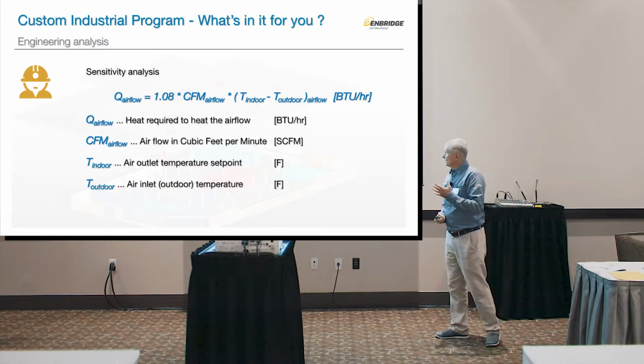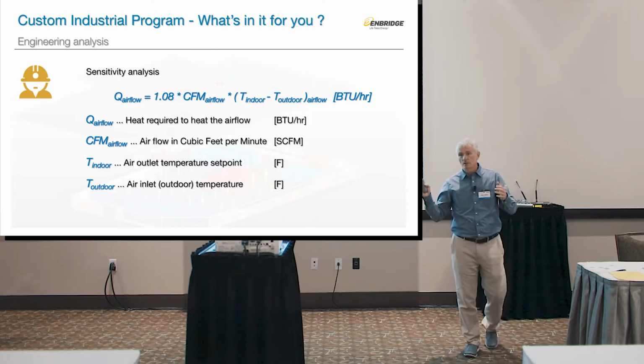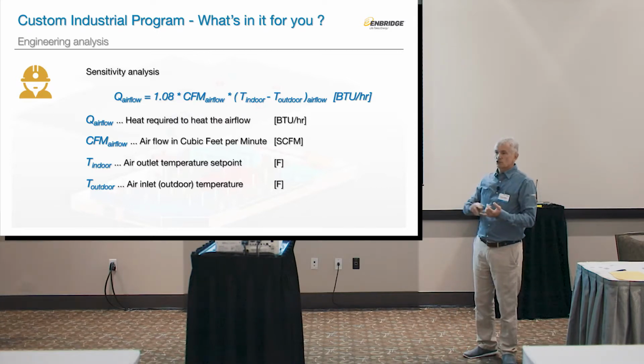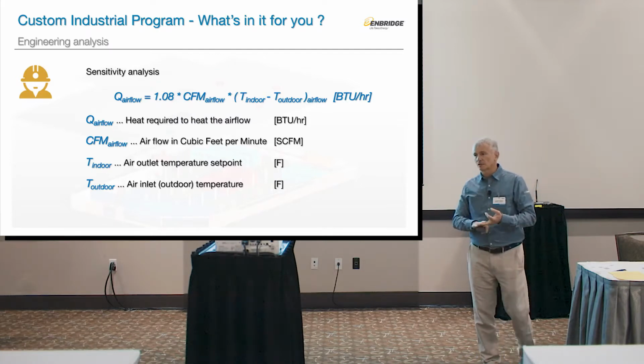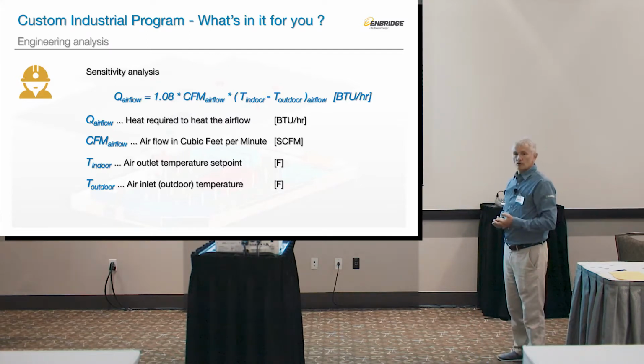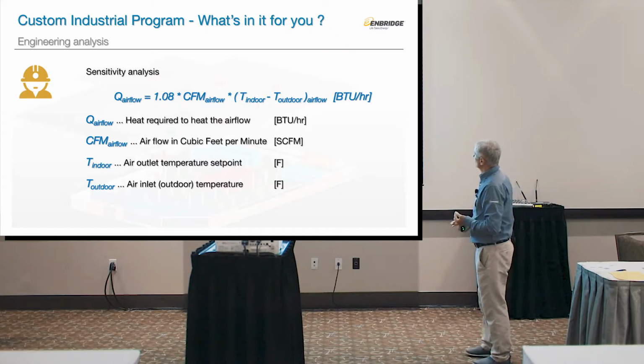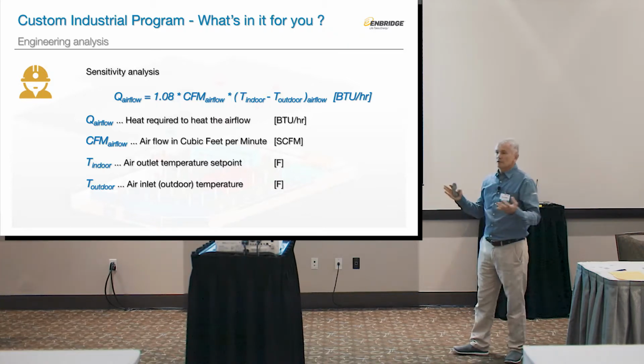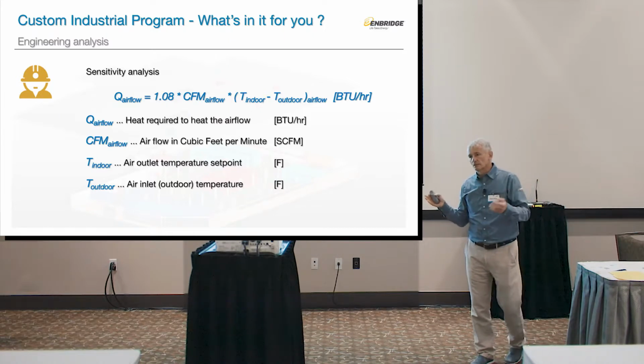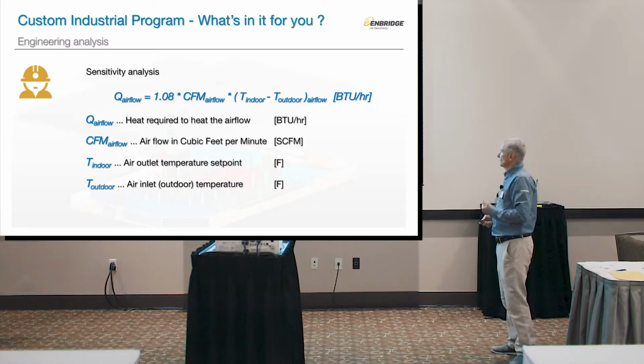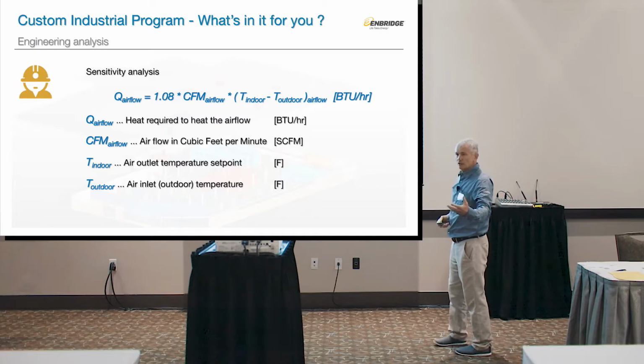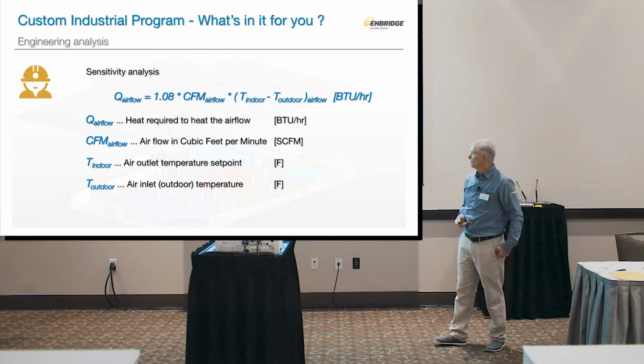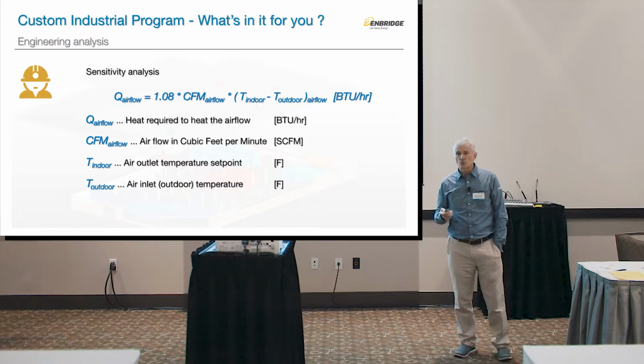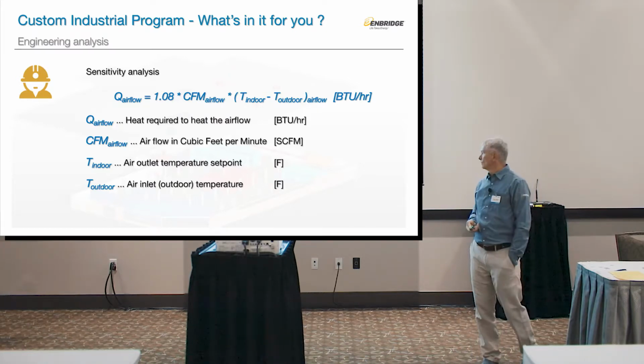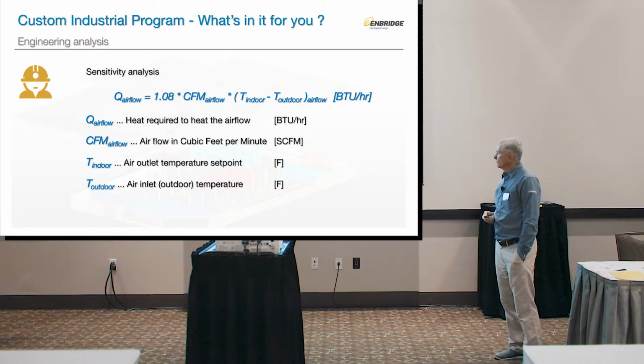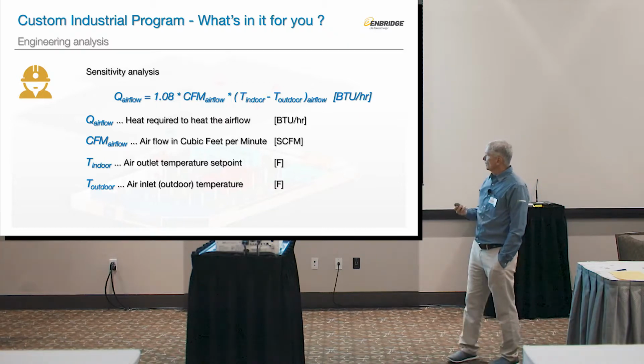So let's look at the sensitivity analysis for this makeup air unit. This formula is essentially mass times specific heat times delta T converted to airflow: 1.08 times CFM airflow times delta T, in BTU per hour. Simple as it gets. Q airflow is the heat required to heat the amount of air that we have. CFM is the airflow in cubic feet per minute that goes through the unit. Indoor set point, outdoor set point.